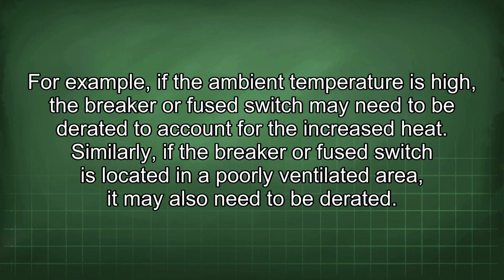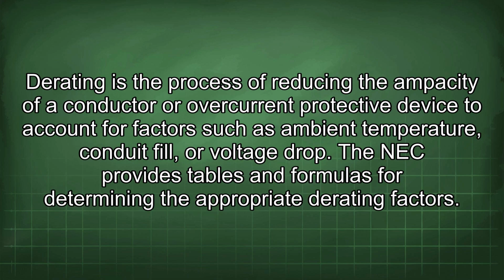For example, if the ambient temperature is high, the breaker or fuse switch may need to be derated to account for the increased heat. Similarly, if the breaker or fuse switch is located in a poorly ventilated area, it may also need to be derated. Derating is the process of reducing the ampacity of a conductor or overcurrent protective device to account for factors such as ambient temperature, conduit fill, or voltage drop. The NEC provides tables and formulas for determining the appropriate derating factors.